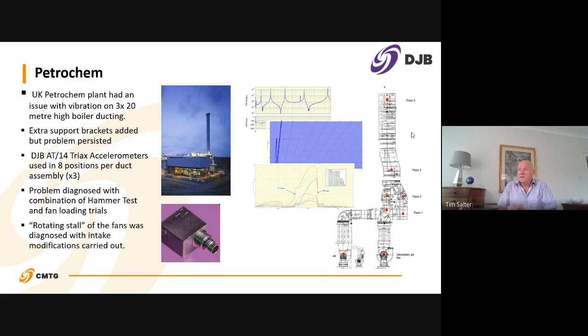So they used the AT14 down here, the triaxial accelerometer, which is a larger version. It doesn't need to be a miniature version to be put on large ducting. First of all, they did quite a complex hammer test. So that's up here, the results of the hammer test, where they had the accelerometers permanently fitted, and they tapped the structure at various places with the hammer to first try to characterize what the resonant frequencies of the structure were. Then they ran the fans at various speeds to see if they could introduce some resonance, but that didn't happen. So the fans were run with no load.